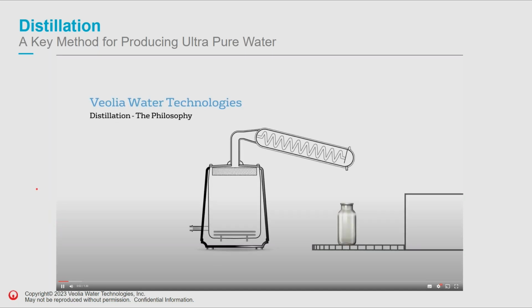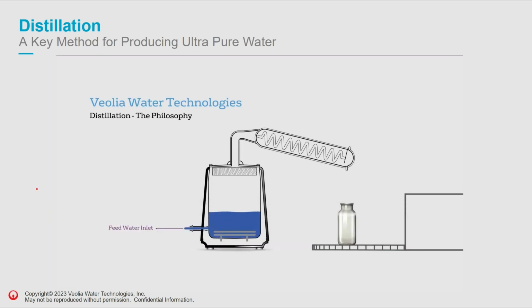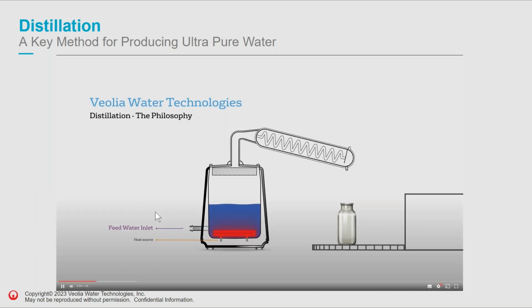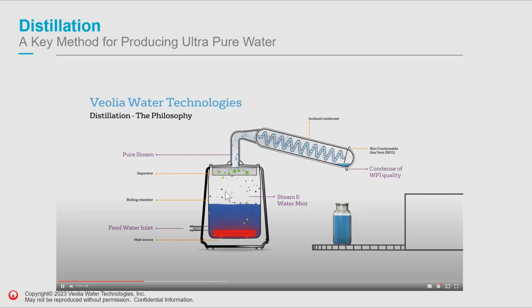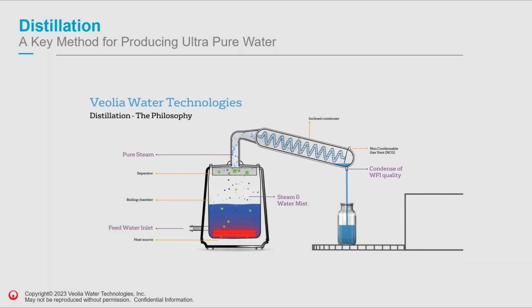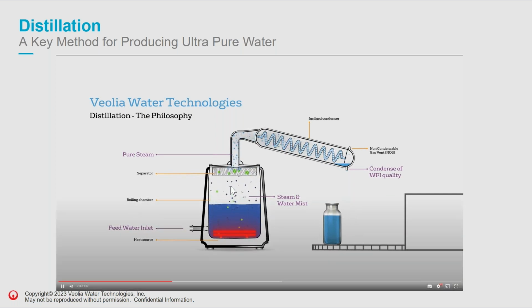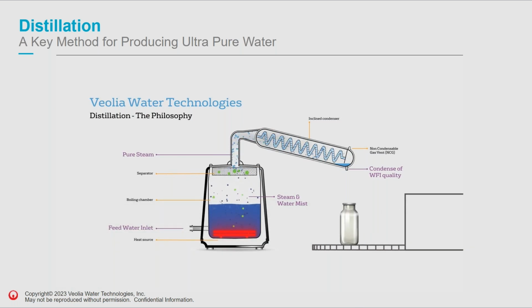So if we look at distillation, which is what we're looking at in particular here, WFI is traditionally produced, as we say, by changing the phase of water to steam. So water comes into the distillation column, it's heated up, either using steam or electricity, mainly steam these days, and then the water turns into steam into this void here. And the key of any distillation system is how you remove the water droplets in that steam and water mist. And it's those droplets that will carry over any impurities into the product.